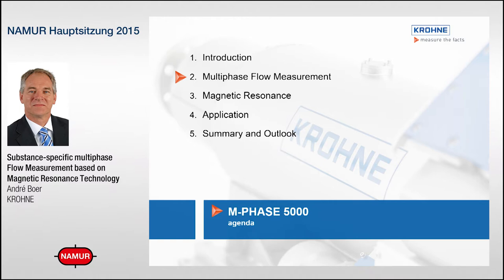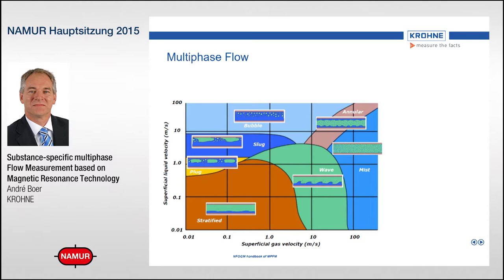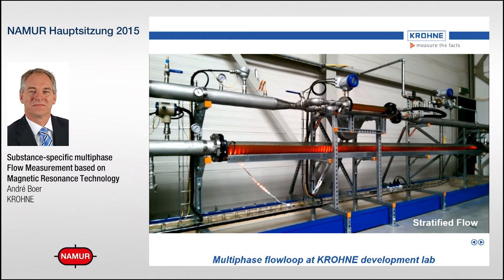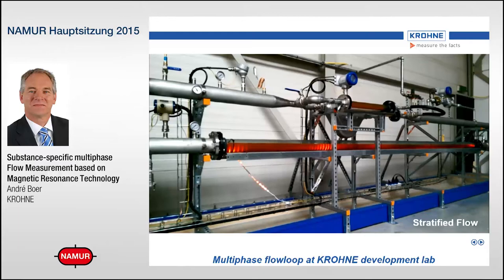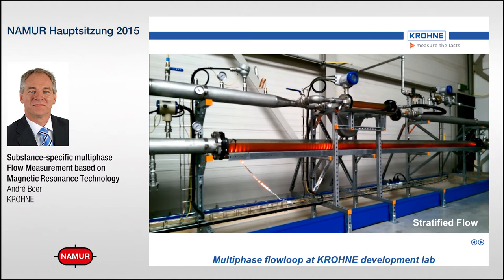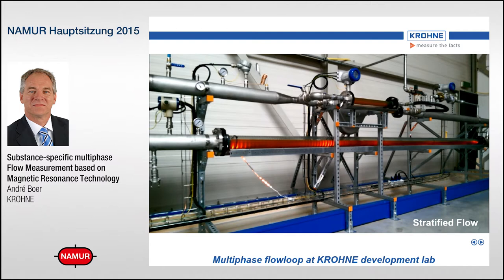Before we go on, I'd like to tell you a little bit more about multiphase flow measurement itself. If you look at multiphase flow, it is often depicted in a graph where on the vertical axis you see the superficial liquid velocity and on the horizontal axis the superficial gas velocity. Depending on the individual velocities of the liquid and the gas, a certain flow regime can occur. Let's start with the stratified flow regime, typically present when flow velocities are quite low. At our factory in Dordrecht, Holland, we have built a small calibration rig capable of demonstrating these individual flow regimes in a multiphase area.